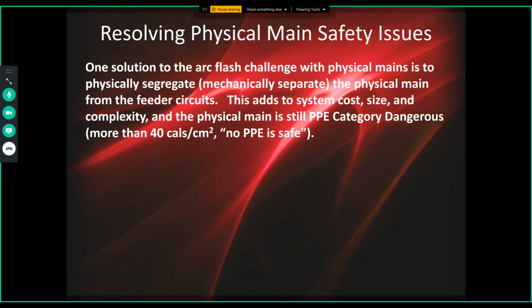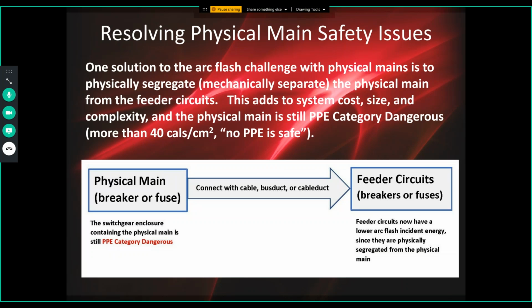So one possible resolution, and this is a legitimate solution, is to physically segregate the secondary main from the feeders when you have a physical secondary main. This does add to system cost. It adds to real estate, and of course, the main device, as is shown here, is still PPE category dangerous. You're still left with a large piece of secondary switchgear which can never be accessed in an exposed, energized manner, which, by the way, makes it problematic even for absence of voltage verification in many cases.